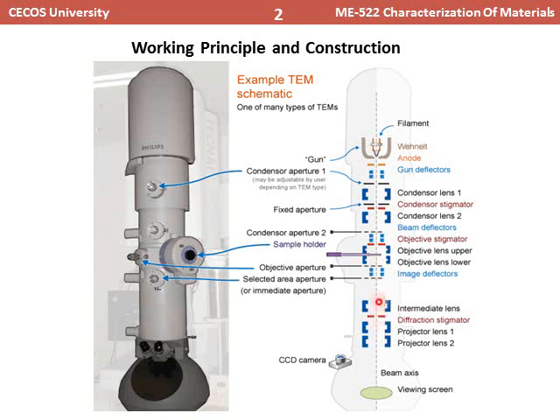After the intermediate lens, the beam passes through the diffraction stigmator, and then through projector lens 1 and projector lens 2, where the beam is focused on the viewing screen. You can view the object of interest either on the viewing screen or via a CCD camera on your LCD or LED screen. Both options are available.